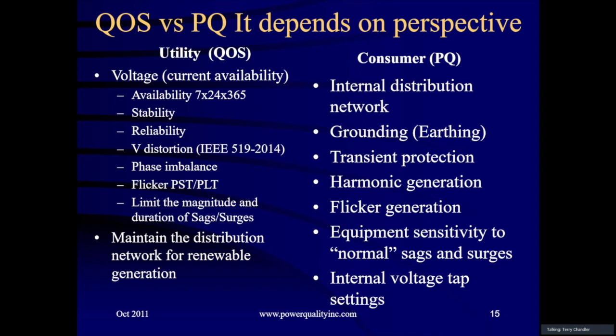From the consumer perspective, while they have the internal distribution network, and there's all kinds of interesting pictures about that, grounding or earthing, if you happen to be from the UK version of this, transient protection, they have to protect their equipment from transients generated by utility switching, but also lightning is the number one cause or number one power quality generator, if we want to call it that, because not only does it generate transients, but it also generates voltage sags. The harmonic generation, as we know, when the power leaves the generator, in general, it's a sine wave, but the harmonics are generated by the loads. So that is a consumer responsibility, not the utility responsibility, but they have to figure out how to limit it.